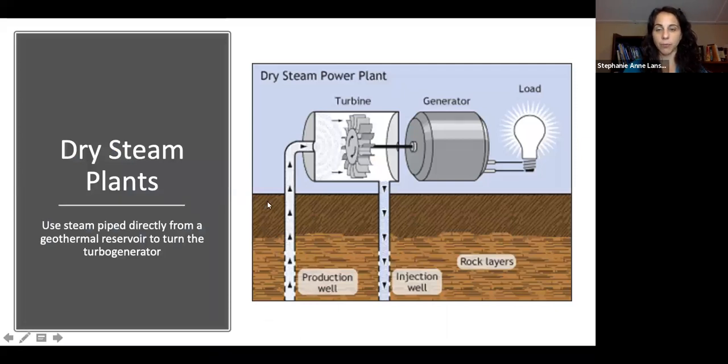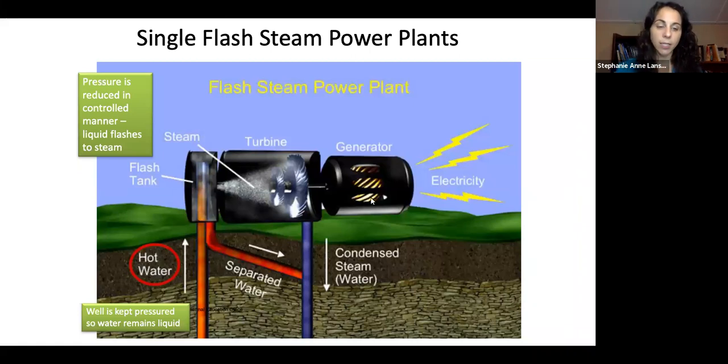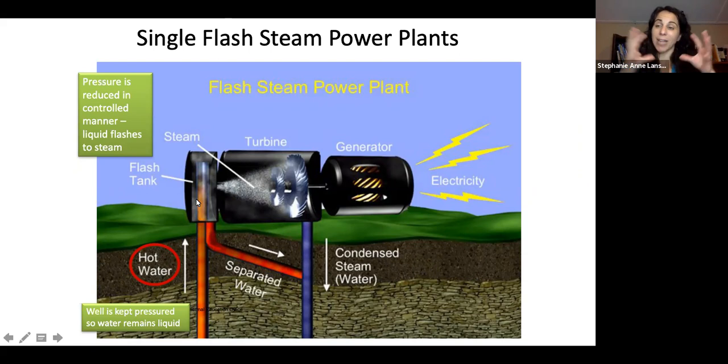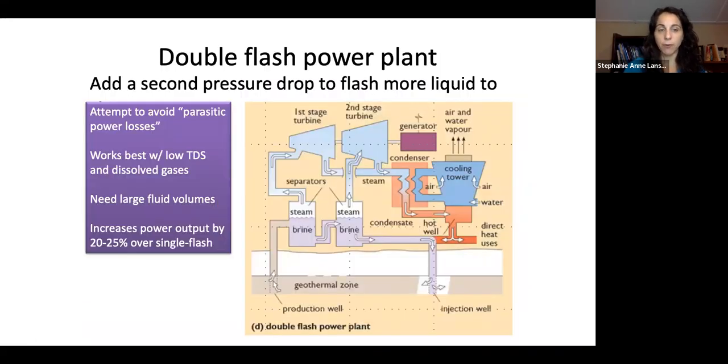Dry steam plants have dry steam moving the turbine and then the injection well—direct use systems for electricity. Single flash systems have hot water and a flash tank where pressure releases the steam. The separated water stays for injection. Double flash with low total dissolved solids and not many dissolved gases can do a first and second drive. It needs larger liquid volumes but can increase output over 25 percent compared to single flash.